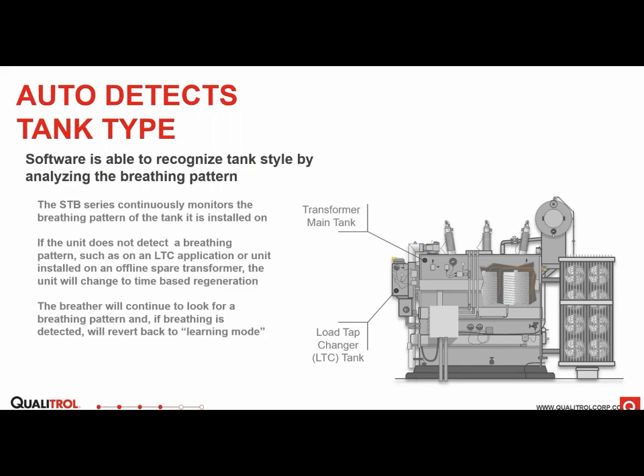And this is continuously done. So if you install it on a transformer and it's not in service yet, once you energize and it starts its breathing cycles, it'll recognize I'm on an LTC, and it'll switch to an LTC regeneration mode. And then at any time, if the breather detects a normal breathing pattern, it'll revert back to a learning mode. Then it'll begin to look for the exhale cycle again, and it will begin to pick a window where regeneration is possible.